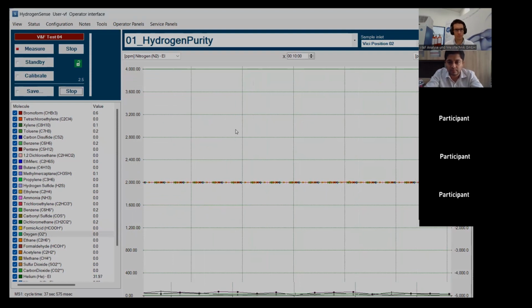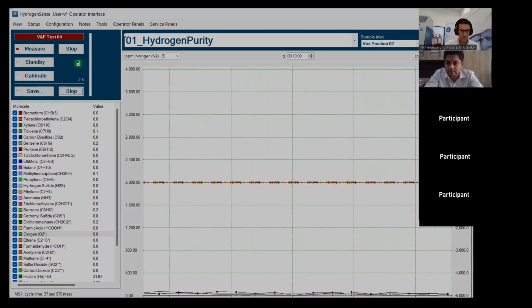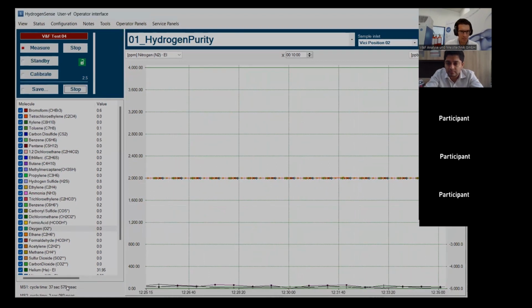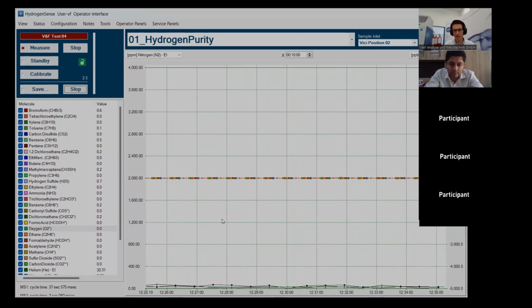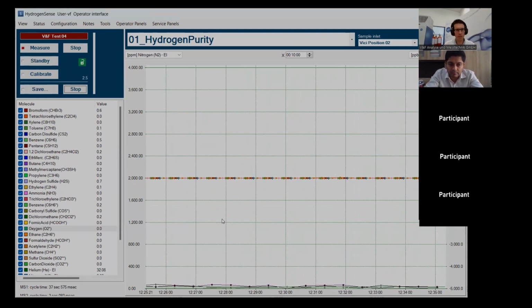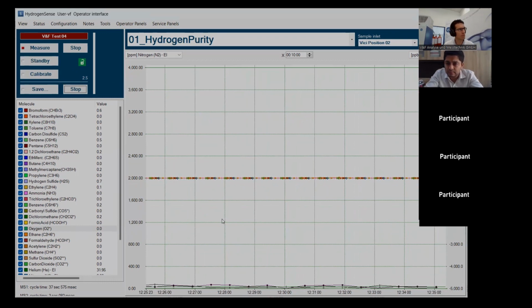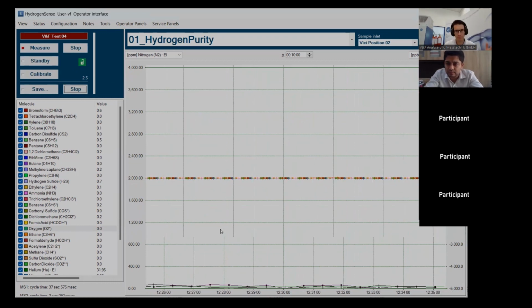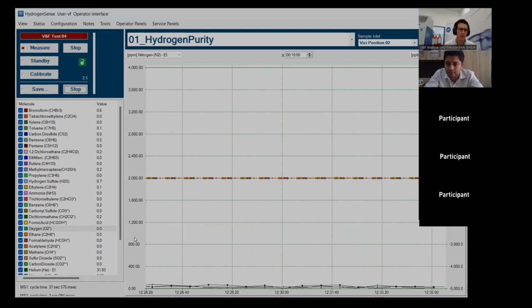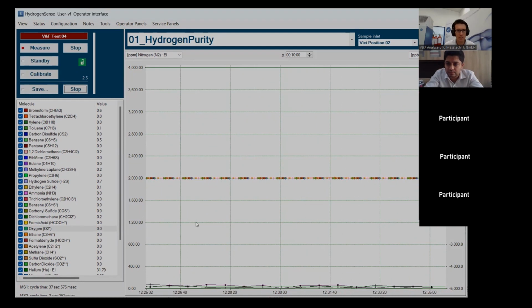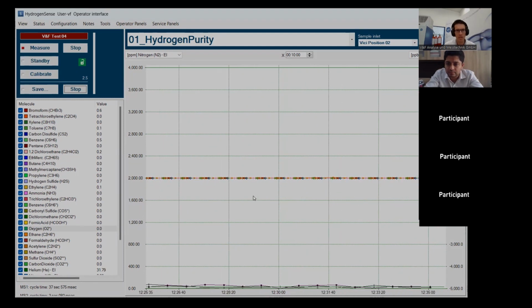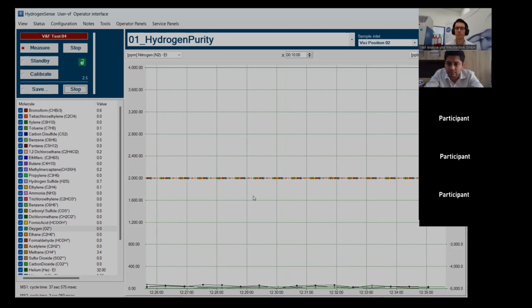And one cycle takes, as you mentioned, I think 30 minutes, right? One cycle is 37 seconds. This is displayed down here. Okay. So if you run 10 points after the flush time, that would take 40 seconds times 10, roughly 5 to 7 minutes. To do it very diligently, we usually say roughly 15 minutes, including the flush time, is what it will take to get a proper measurement result. Okay.